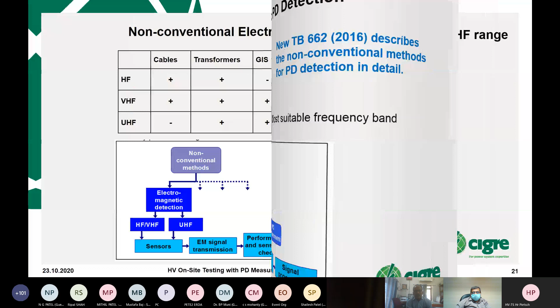Here are the highlights of electromagnetic PD detection at higher frequencies. For cables, high frequency means more than 50 Hertz, several kilohertz. Very high frequency means, in this context, several tens of megahertz. Ultra high frequency is now increasingly applied to transformers. It started 30 years ago with GIS, and these frequency ranges are also used for generators.